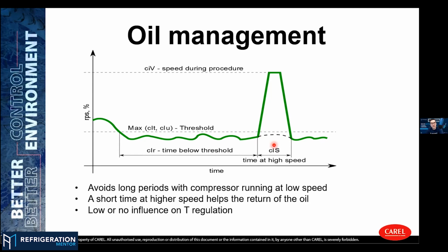Awesome. If you run into this, are there certain numbers that will come up on the drive to say that, okay, we're in oil management ramp up speed, or is there anything that will let a technician know that that's happening? Most of the controllers will pop up a message on the main screen saying status. Instead of compressor on, it will be oil booster or oil recovery procedure, something like this. Most of them come with a message saying you are speeding up the compressor for some reason, and it will be shown over there.